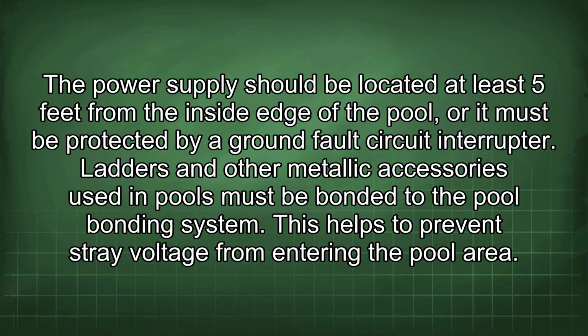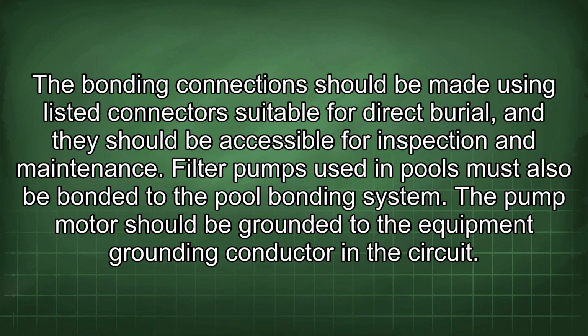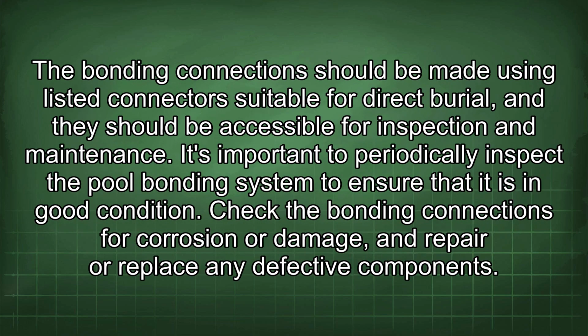Ladders and other metallic accessories used in pools must be bonded to the pool bonding system. This helps to prevent stray voltage from entering the pool area. The bonding connections should be made using listed connectors suitable for direct burial, and they should be accessible for inspection and maintenance. Filter pumps used in pools must also be bonded to the pool bonding system. The pump motor should be grounded to the equipment grounding conductor in the circuit. The bonding connections should be made using listed connectors suitable for direct burial, and they should be accessible for inspection and maintenance.